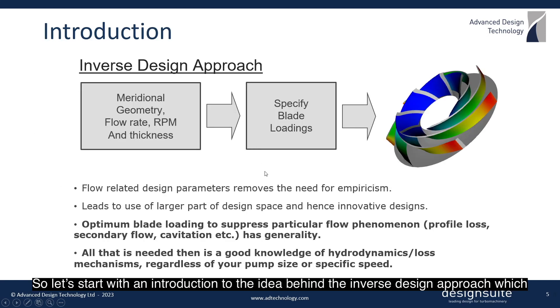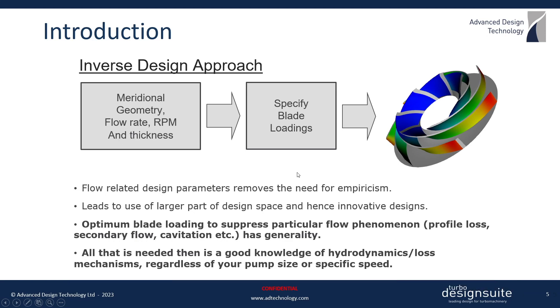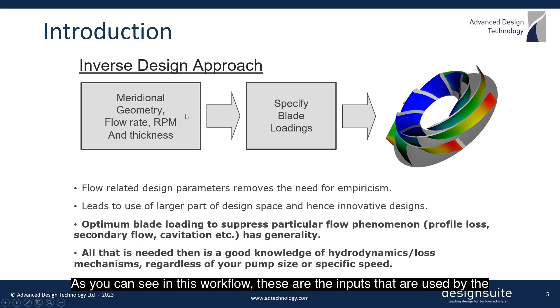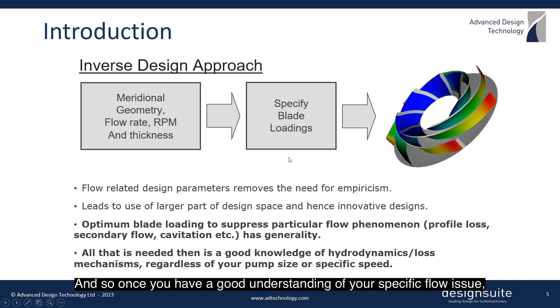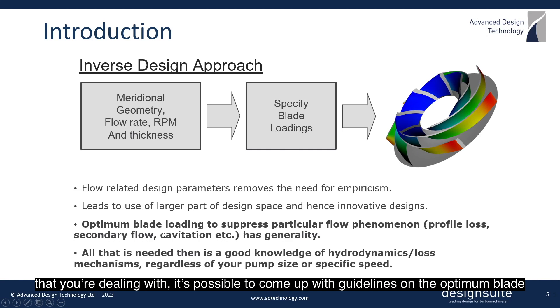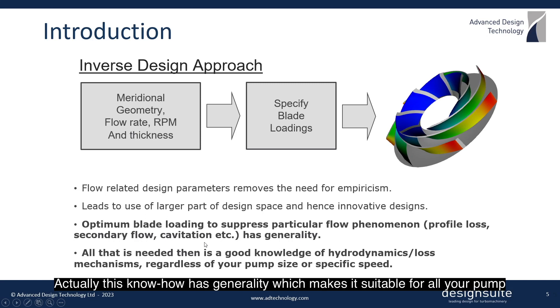Let's start with an introduction to the idea behind the inverse design approach used throughout this presentation. As you can see in this workflow, these are the inputs used by the inverse design method to give us the final blade design. Apart from some basic parameters, these blade loading inputs are really flow related. Once you have a good understanding of your specific flow issue — whether it's profile or secondary flow or cavitation — it's possible to come up with guidelines on the optimum blade loading to tackle each of these issues. This know-how has generality, making it suitable for all your pump applications.